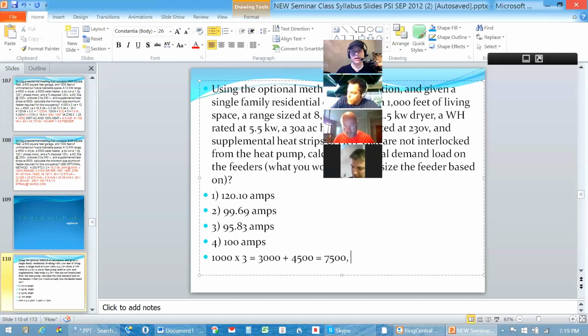And then I moved down the list there. The range is 100%. The dryer is 100% of 4,500. The water heater is 100% of 5,500. I mean, everything else in that question is just 100%. So I'm going to end up adding 8.5, 4.5, and 5.5 to that, just straight across the board. So plus 8,500, plus 4,500. And this is the nice thing about the optional method, man. I'm telling you, you just start adding stuff in there. You don't have to worry about it. And then the water heater, 5,500.